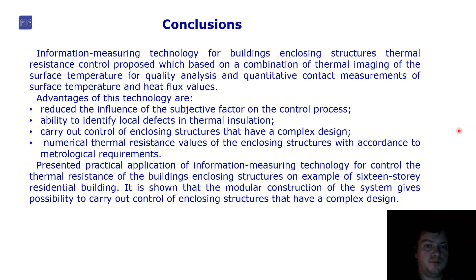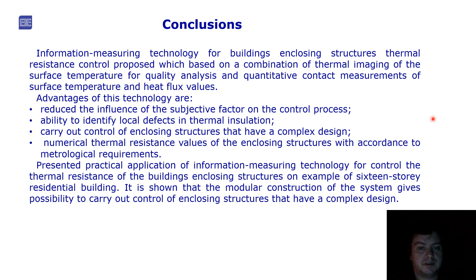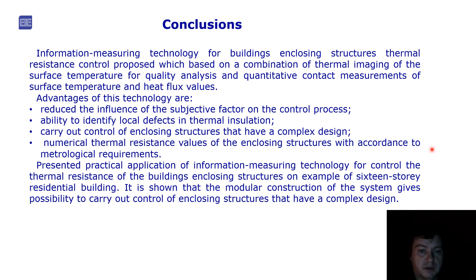Conclusions: The information-measuring technology for building enclosing structures thermal resistance control proposed is based on the combination of thermal imaging and quantitative analysis based on contact measurements of heat fluxes and surface temperature. Advantages of this technology are: reduced influence of the subjective factor on the control process, ability to identify local defects in thermal insulation, control of structures with complex design, and numerical thermal resistance values of enclosing structures in accordance with metrological requirements. The paper also presents a practical application on a 16-story building. Thank you for your attention.